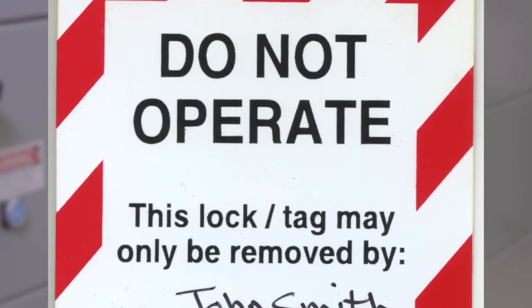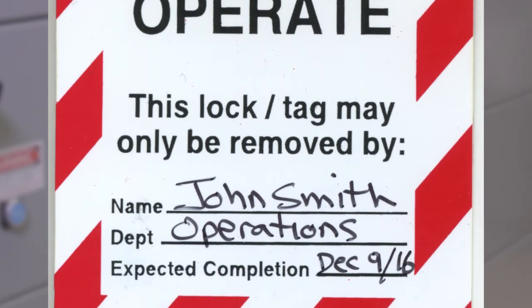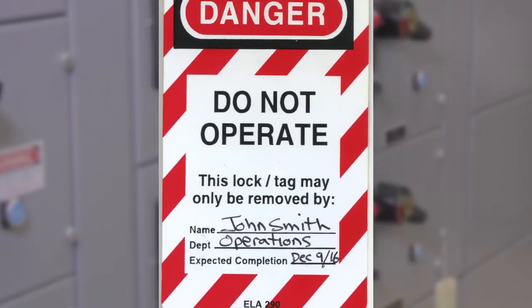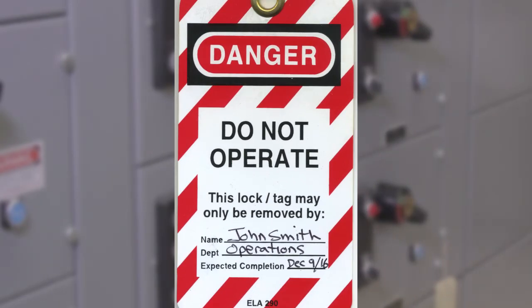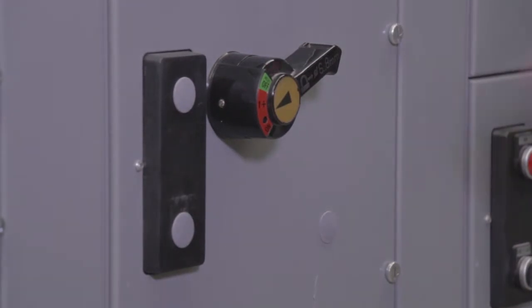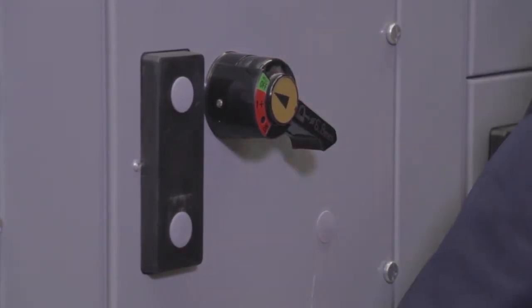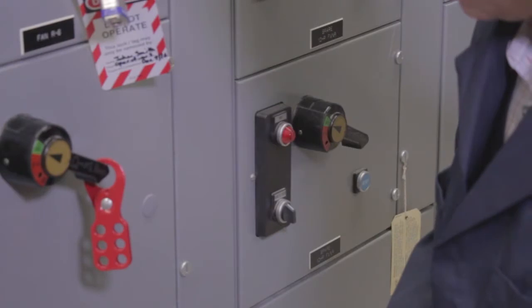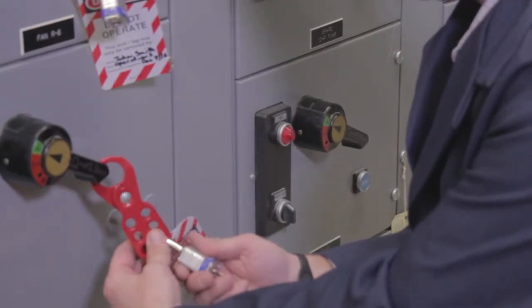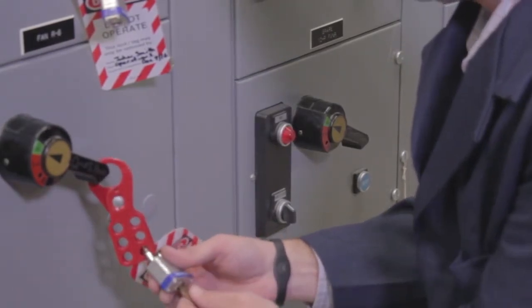Tags are crucial because they identify who locked the equipment out, the date it was locked out, department or location, and the reason. Tags may have different styles, but they all have the same information. You may have to lock out more than one energy source in order to work on one piece of equipment. Only one person is put in charge of a lockout/tagout to prevent confusion and accidents. You applied the lock, therefore you are responsible.